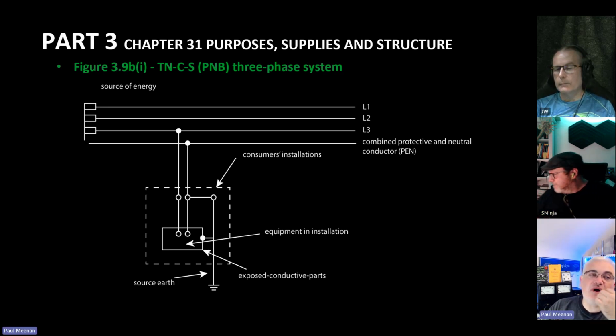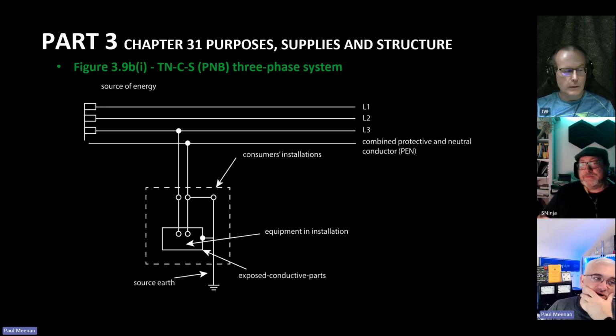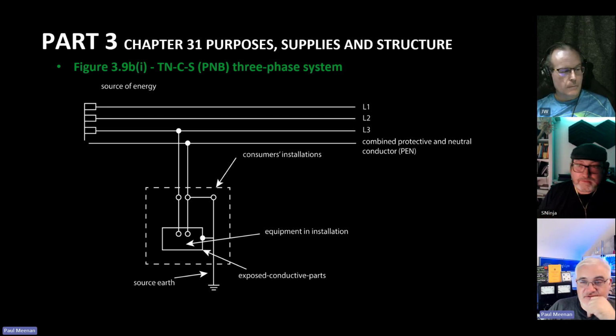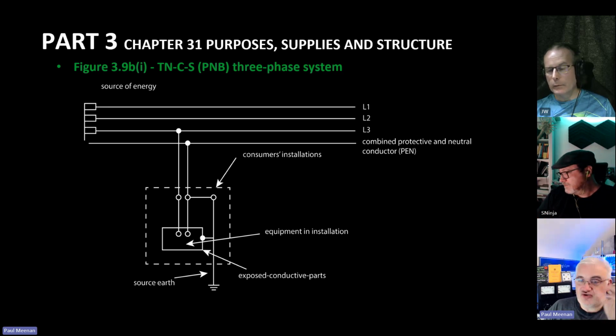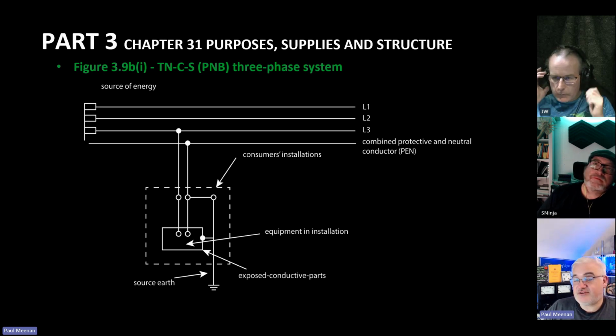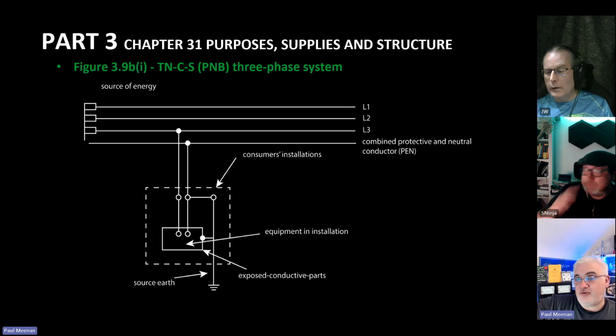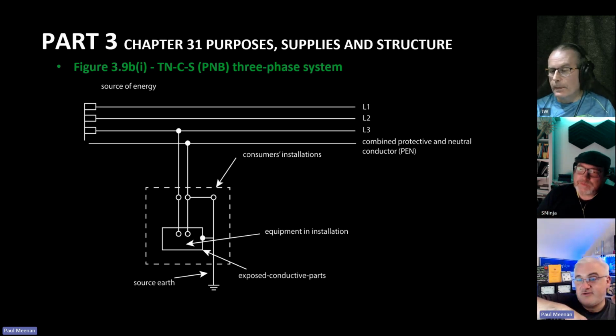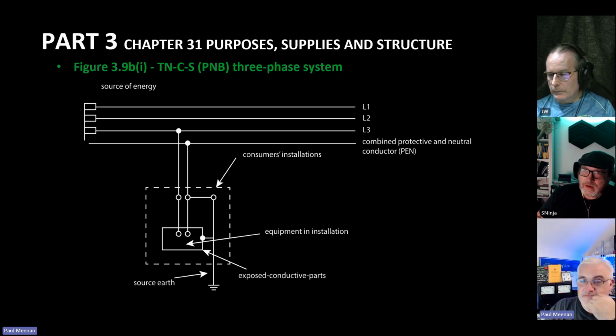Yep. One other alteration is in part 3, where you've got the diagrams of all the different systems. The TNCS PNB 3-phase system is in there. It's on the screen, where the neutral and earth are linked within the installation. A perfect example of that is actually Blackwall Station on the DLR, where you've got a transformer on one wall, and next door to it you've got a big LV panel, nice solid copper bars, neutral and earth solid link. Yeah. And that's what does that station.